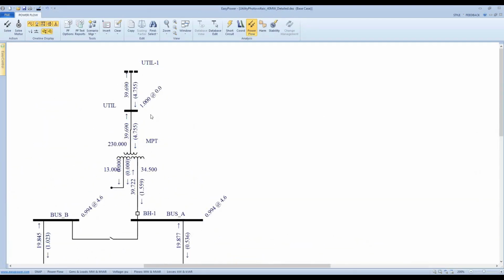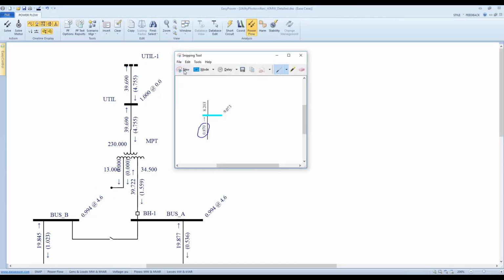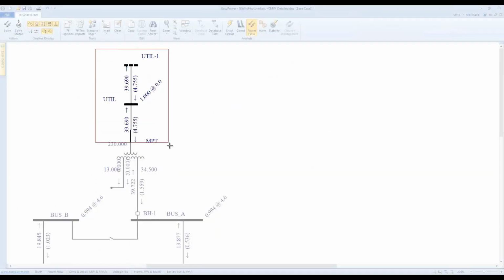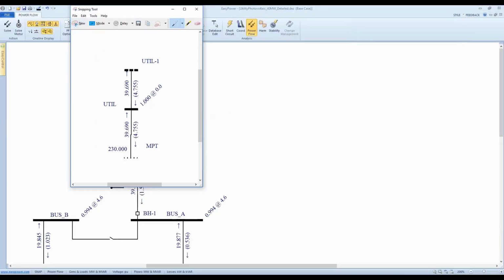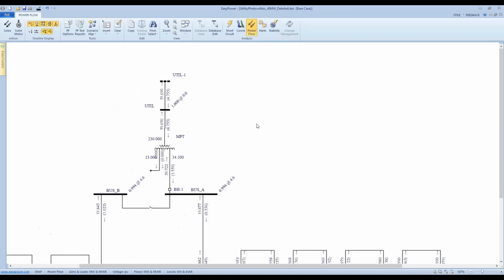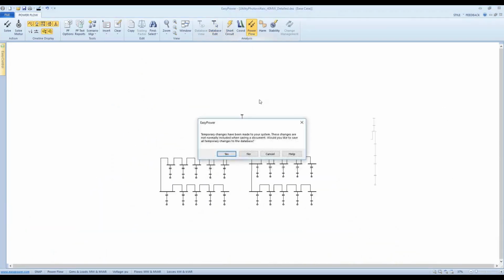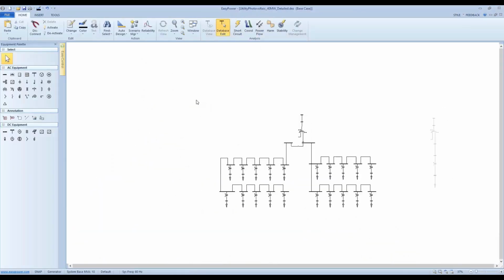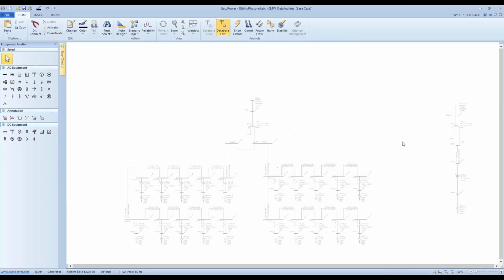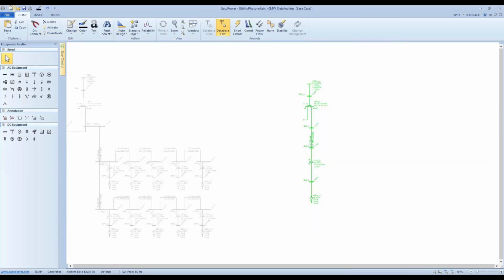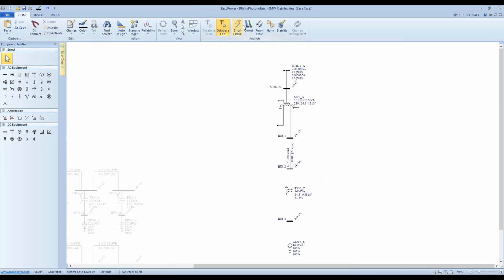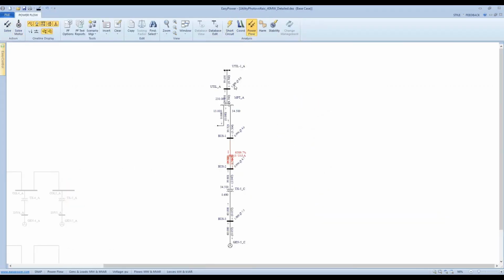Now the power flow result looks like this. We need to keep in mind this number. So let's just take a snapshot of those. The 39.690 is the active power delivered at the utility bus, the high side of the substation transformer. Let's see if we can get the same number from our equivalized model. So take this, deactivate, activate this, run the power flow, solve.